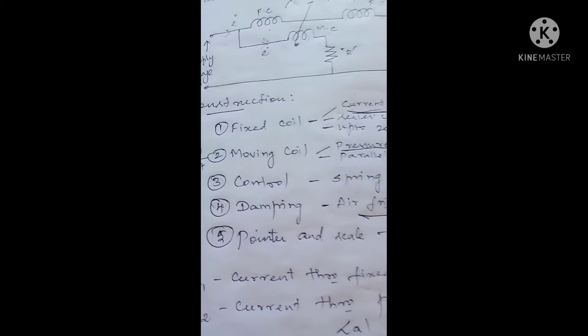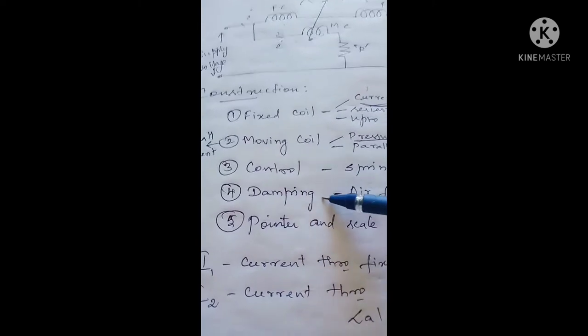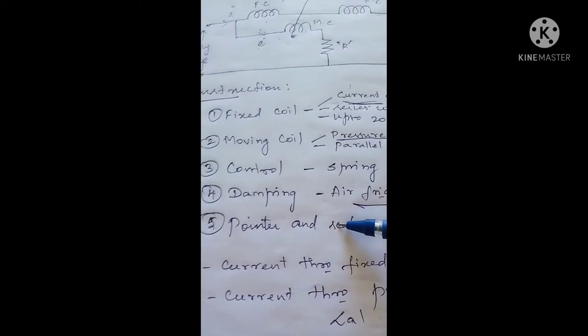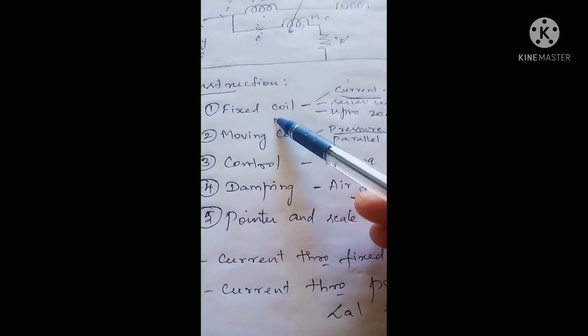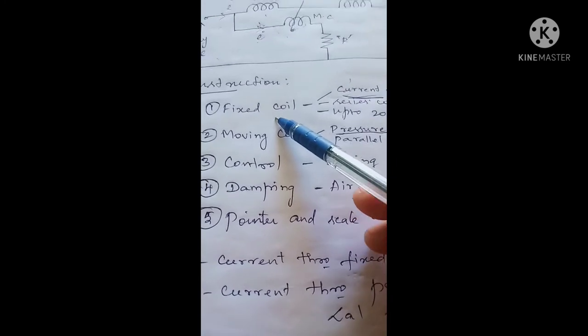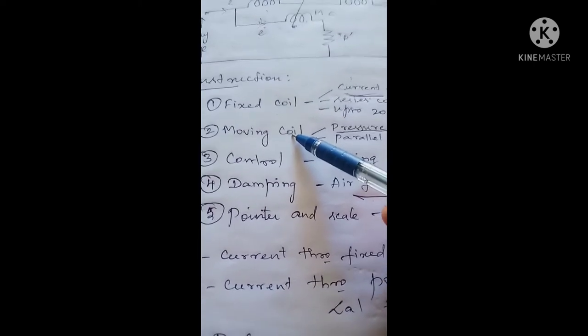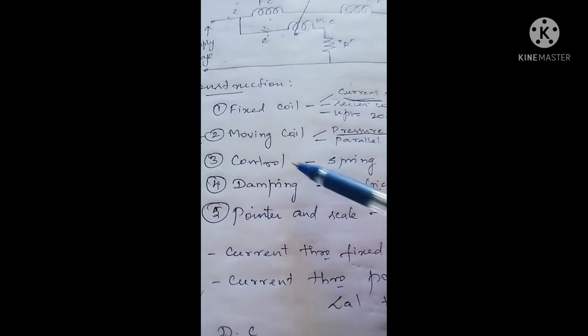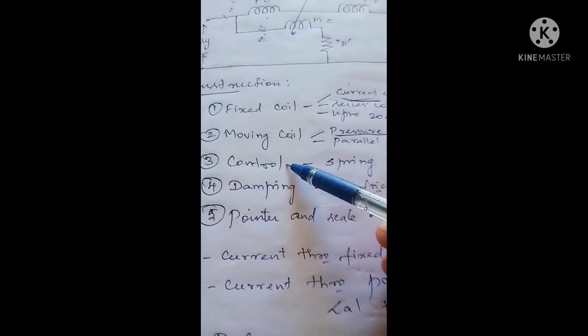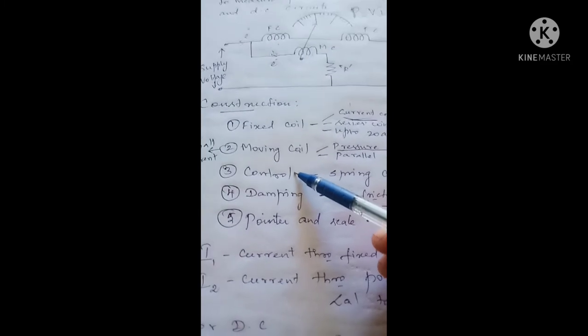The five main parts of the electrodynamometer wattmeter are: fixed coil arrangement, moving coil arrangement, control arrangement, damping arrangement, and pointer and scale arrangement. The fixed coil is connected in series with the load so it's called the current coil. The moving coil is connected in parallel with the supply voltage so it's called the pressure coil.